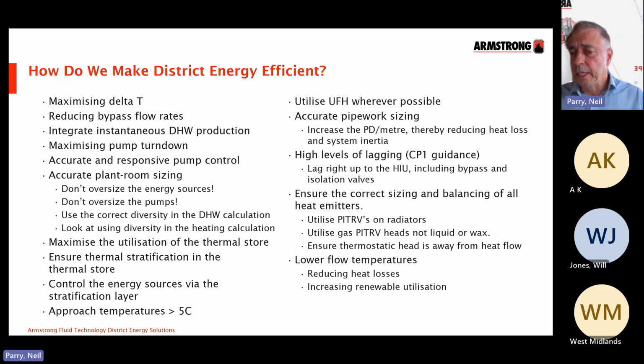And then finally, look at lower flow temperatures. We have to be mindful that as we lower that flow temperature, the return temperature will come up a little bit. But the benefits of lowering that flow temperature and the reduced losses on the network do actually outweigh that slight reduction in delta T.